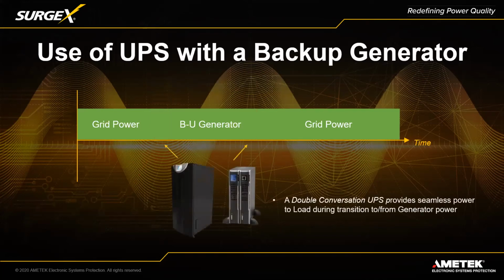If you advance, Justin, you can see that when you use a double conversion online UPS in conjunction with a generator, it smooths out those transition periods, and your equipment never sees any downed power. We're seeing a lot of this in high net worth residential applications, where they use a generator as well as a large format, or multiple large format, double conversion UPSs, so that all the power in the house is completely treated and conditioned.